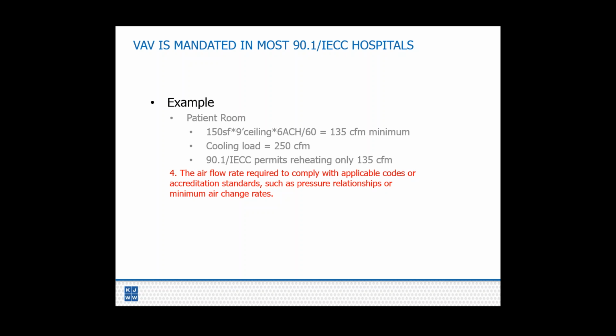So here's an example in a patient room. I chose a 9-foot ceiling and a code minimum 150 square foot room in this case. So I have 135 CFM minimum flow that I have to maintain. And let's say my cooling load on the peak day is 250 CFM. So what that really says is I can only reheat 135 CFM by ASHRAE 90.1 or IECC 2012. So that means I am a VAV system. I mean, that change to the reheat requirements basically made constant volume hospitals not in compliance with code in areas that use those energy codes.